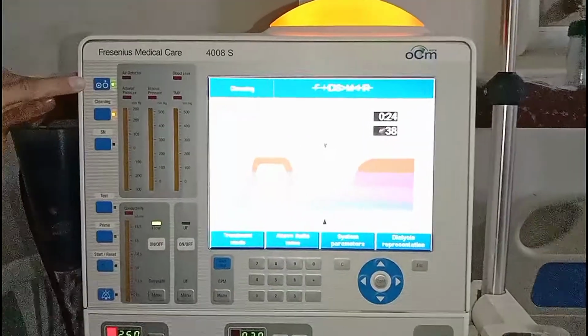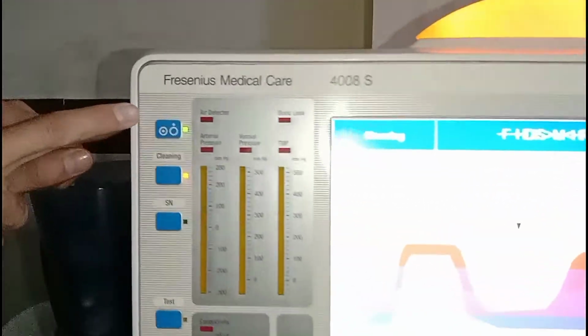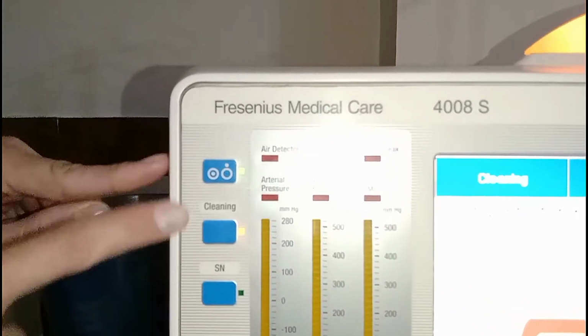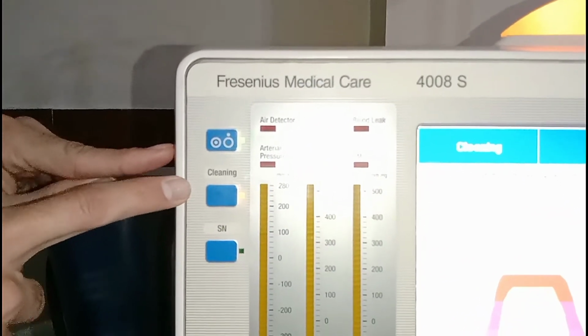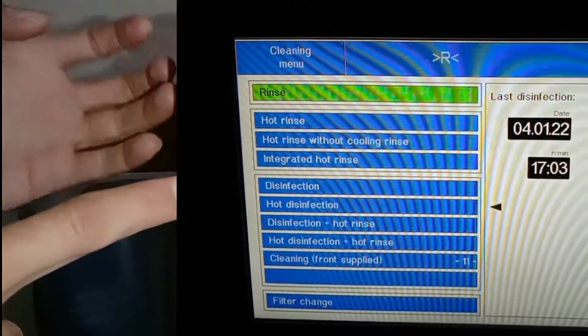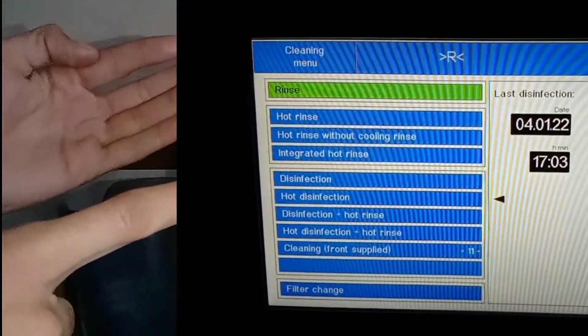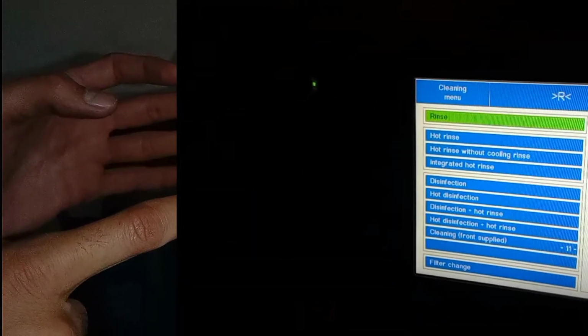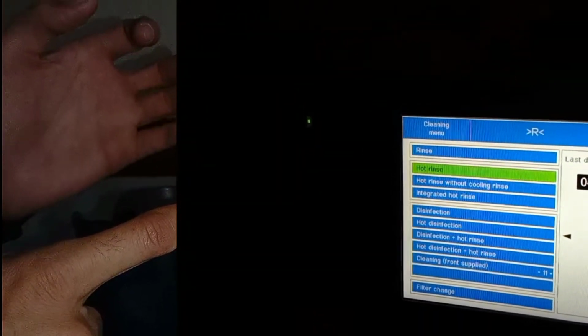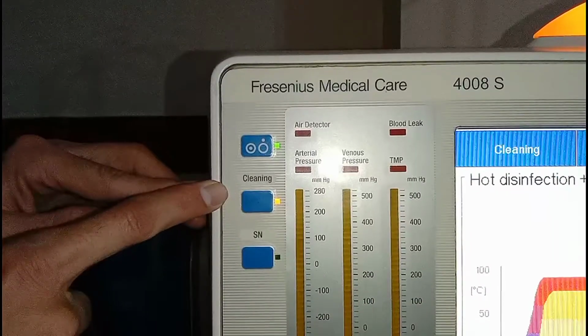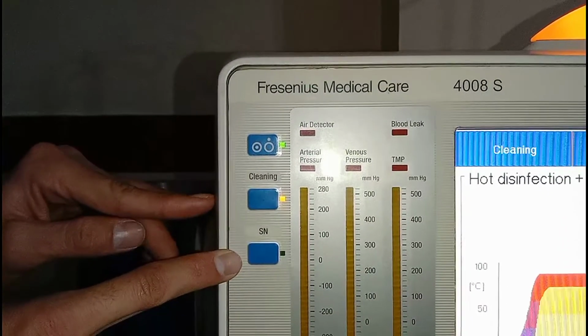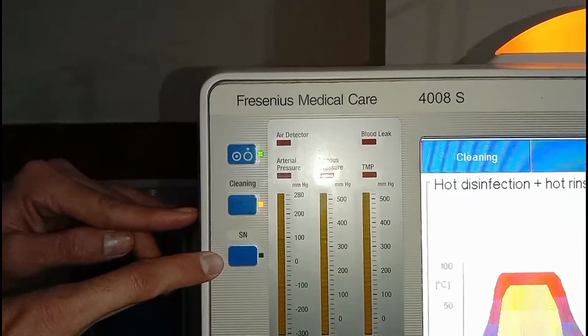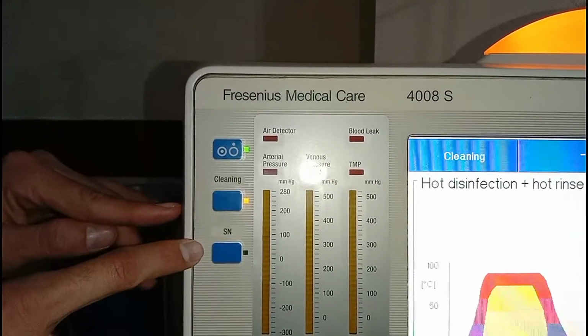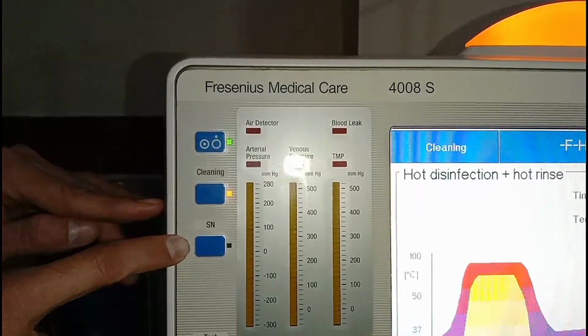On the top there is the on and off button, and below it there is the cleaning option. In cleaning there are different maneuvers that you will see on the screen: rinse, hot rinse, disinfection, and hot rinse plus disinfection. There are different indications for these maneuvers that I will cover in a separate video. Below the cleaning option there is the single needle option, which is used in case of single needle dialysis, and most of the time it is not used here.